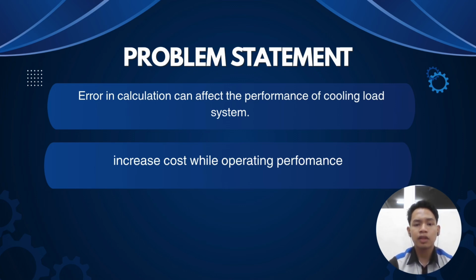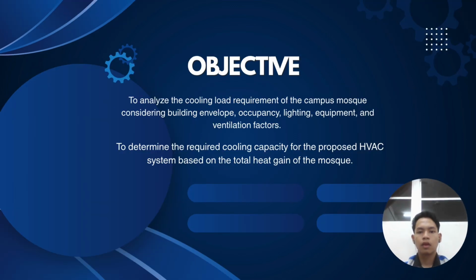Third, and most importantly for an engineer, any error in the initial cooling load calculation can completely degrade the performance of the HVAC system. If the system is oversized, it leads to rapid short cycling, high energy waste, poor humidity control, and high upfront installation costs. If it is undersized, the system will run continuously without ever satisfying the room's comfort requirements, leading to high maintenance costs and occupants' discomfort. To solve these precise issues, I have established two clear measurable objectives for this study.